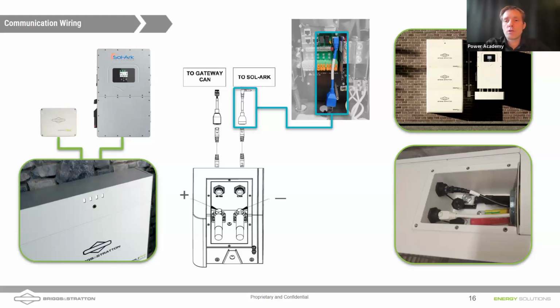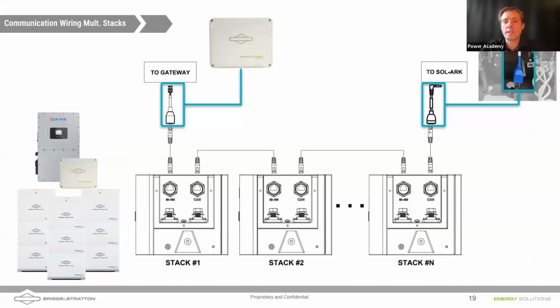And that's it. Your 2 comms connections, and then you have that DC battery connection coming off of those two cables. So the home runs on the battery, and then just two comms cables. In fact, if you're not using the Energy Track gateway, you would just have a single communication cable running to the Sol-Ark. So pretty easy overall wiring here. If you had multiple battery stacks, you would want to have a combiner to combine those battery power outputs. If you just had two stacks, you could use the Sol-Ark dual inputs as a combiner. But three or more stacks, you would want a combiner.